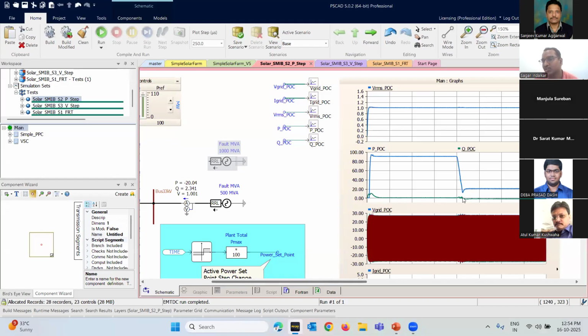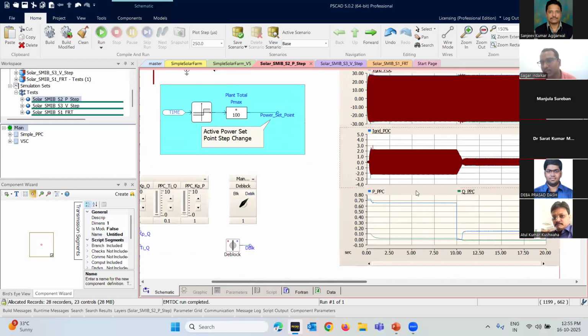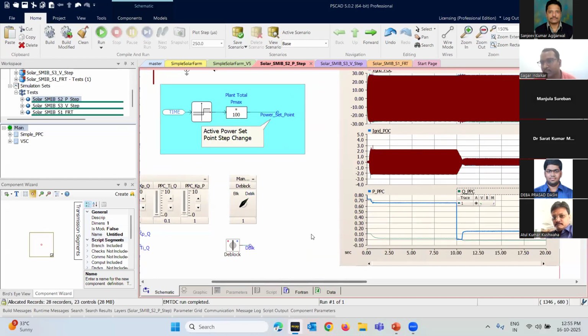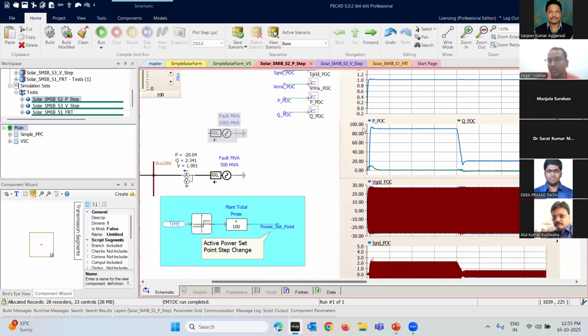Similarly, we did not make any changes to reactive power, but there is a small dip in the reactive power because of injecting additional active power. There was a minor change in the voltage at the POI, and because of that you'll see a small change in Q as well. Similarly, this is your PPC command order from the PPC, which will go to the inverter. This blue is active power command, green is reactive power command, and then you have to correlate whether the inverter is correctly following it or not, and whether there is instability or other compliance issues with the response of this model.